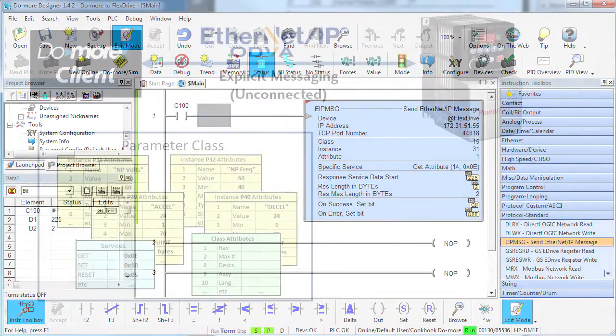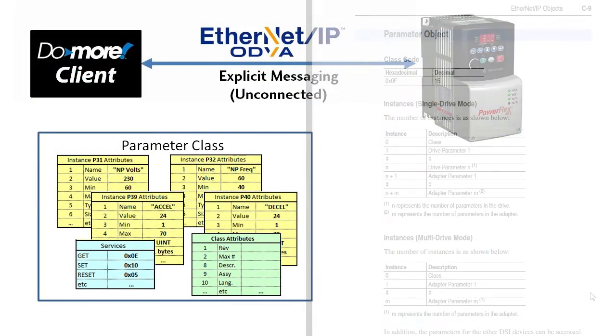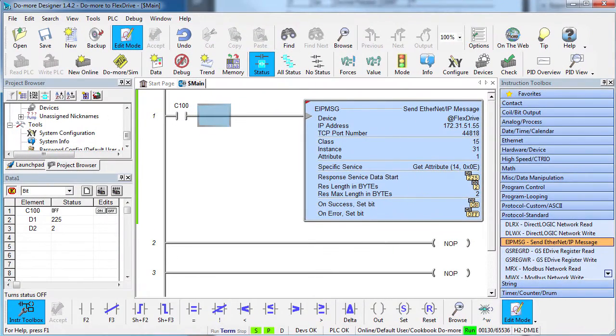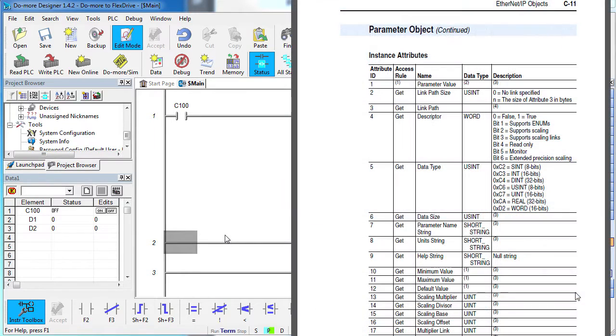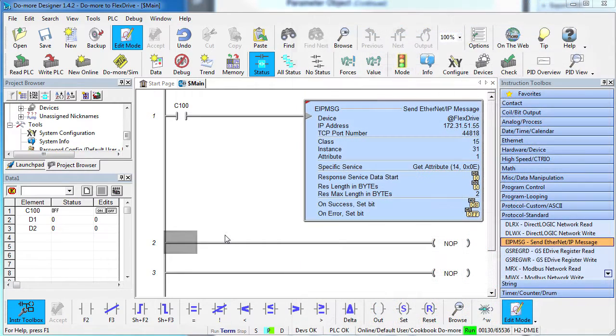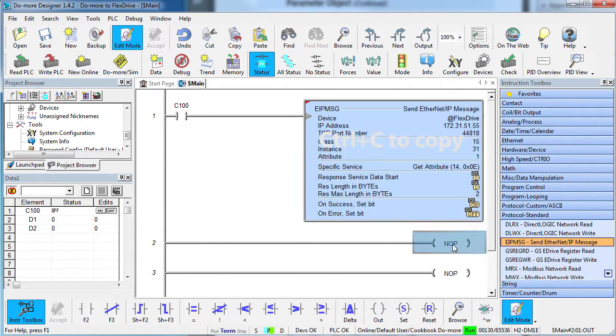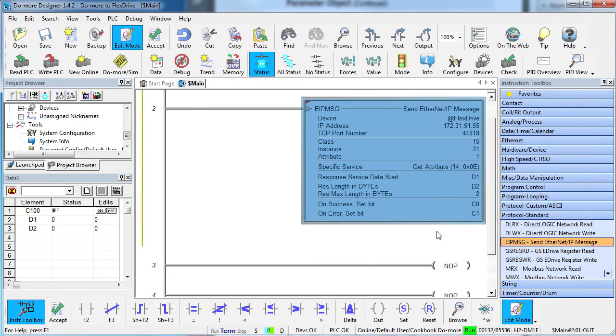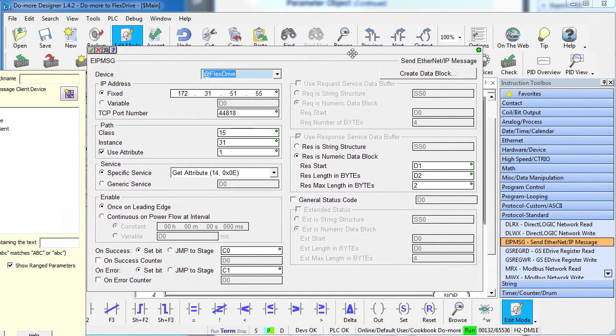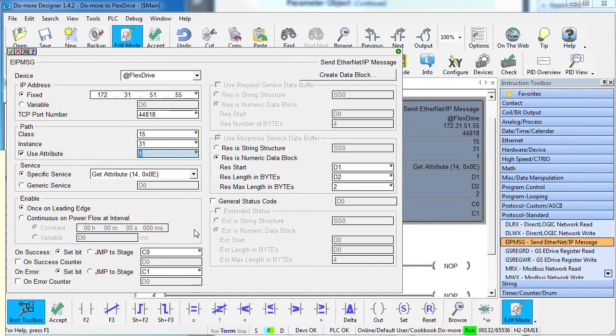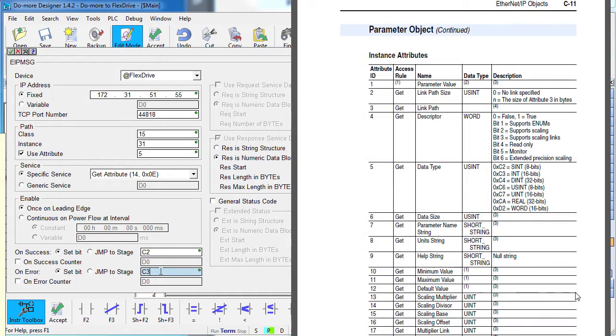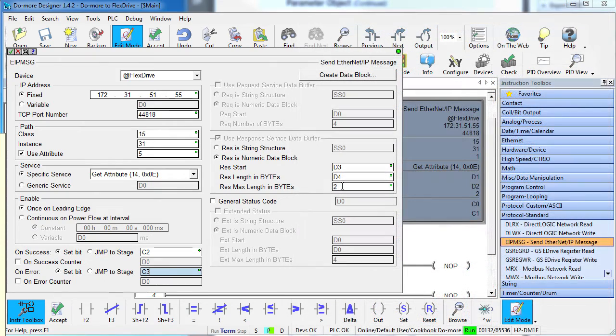Well, that's all there is to it. Given these tables, we just look up what we want and fill in the blanks. Ethernet IP is easy once you understand how to navigate these tables. Now, how did I know that that nameplate voltage was an unsigned 16-bit integer? Well, I asked for it. You can see back in Appendix C that the data type is attribute number 5. Let's try that. And since it's almost the exact same thing as we just did, let's just copy that instruction and modify it. The only thing we need to change is the attribute we want. Instead of the parameter value, we want the data type, which is number 5. And let's put that result in D3 and the length in D4 and let's use these for our success bits. We see in Appendix C, attribute number 5 is an unsigned integer of 8 bits so we only need one byte for that. Click OK.